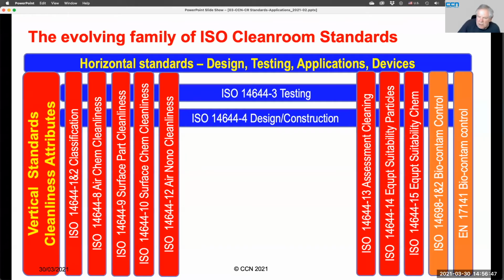Now, part 4, which I'll use quite a lot in the section on thinking through the application of these standards, covers design, construction and startup of cleanrooms. This is currently in major revision, so I'll explain a little bit about that evolution when we come to it. But it's a really important standard that takes you through a logical progression from concept and need through user requirement, design, building the installation, starting up and commissioning it, and going through verification and so on. If you're in the life science sector, you would be able to fit all the Annex 15 qualification and validation principles into this standard. The good news is it doesn't even mention the word validation in it. So it's written in a way that can be applied in a flexible way to any procurement of a device or a more complex clean room. So part 4, very important standard.